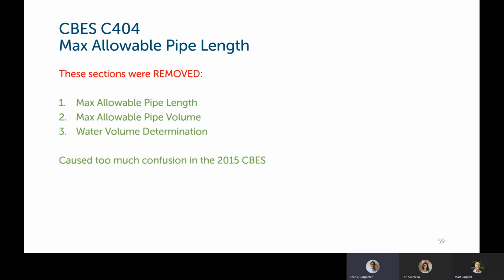In this version of the code, the maximum allowable pipe length section has been removed completely. This is pretty good news. I know there was a lot of confusion in the 2015 commercial code with the allowable volume and length of the hot water piping that you could have for the hot water supply. It was pretty hard to meet those requirements, so that has just been removed from this version of the code altogether.